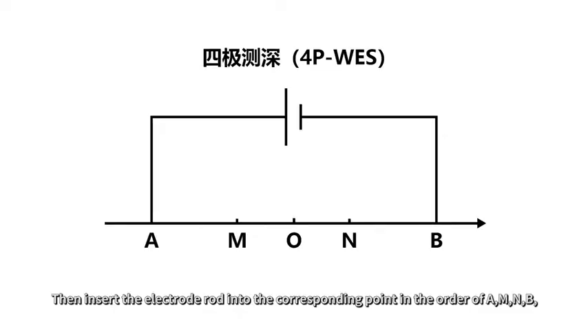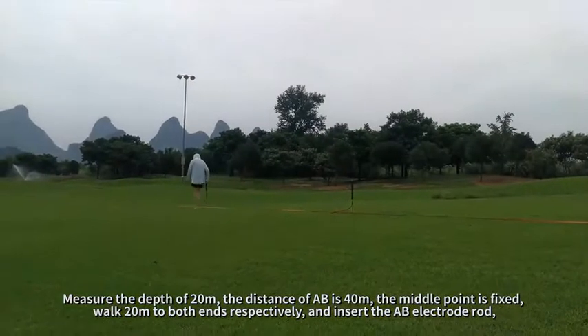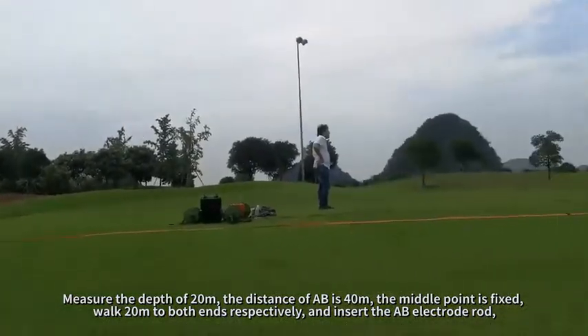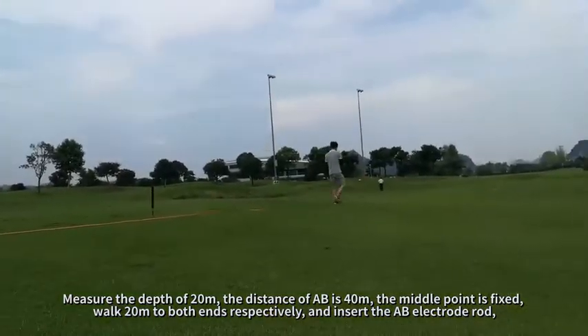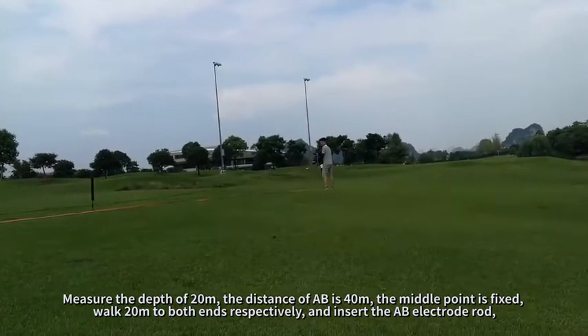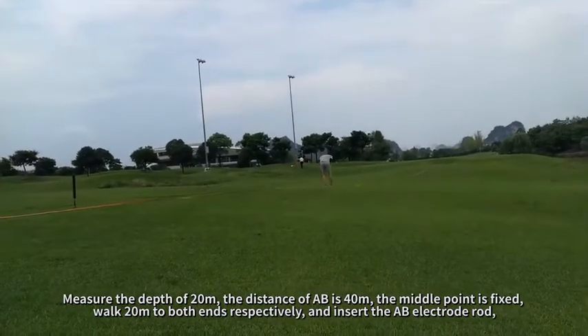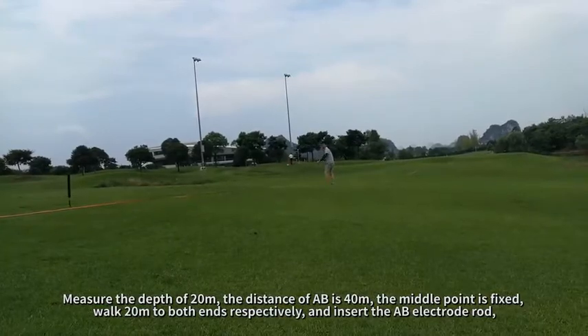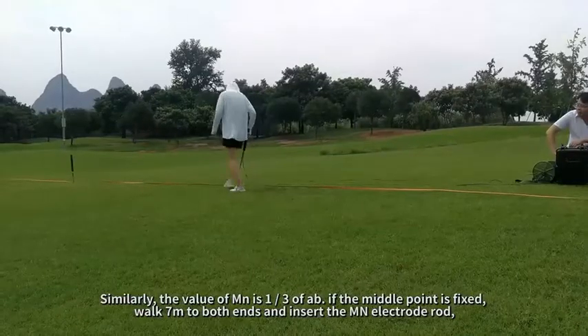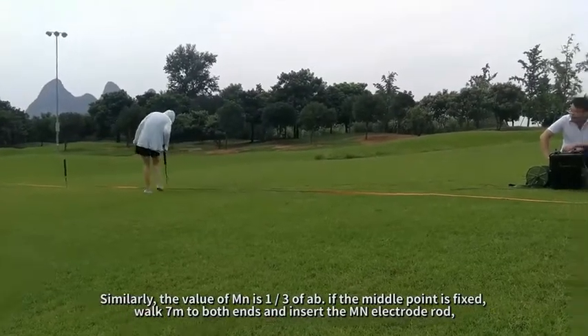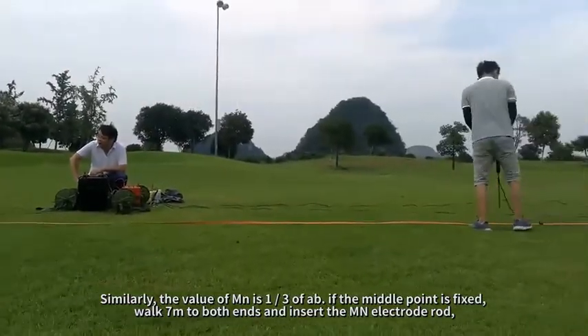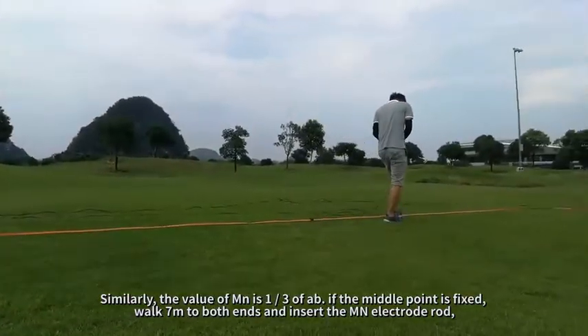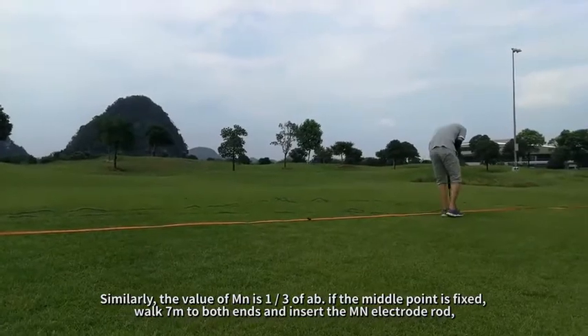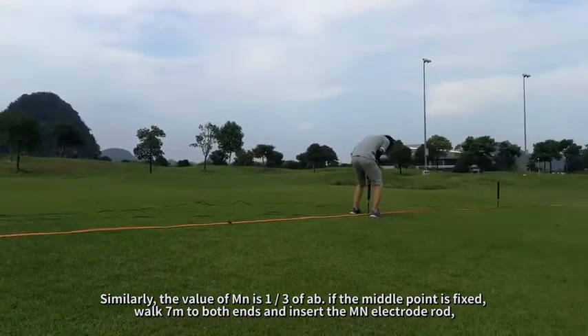Then insert the electrode rods into the corresponding points in the order of A, M, N, B. Measure the depth of 20 meters. The distance of AB is 40 m. The middle point is fixed. Walk 20 m to both ends respectively, and insert the AB electrode rod. Similarly, the value of MN is 1/3 of AB. The middle point is fixed. Walk 7 m to both ends and insert the MN electrode rod.